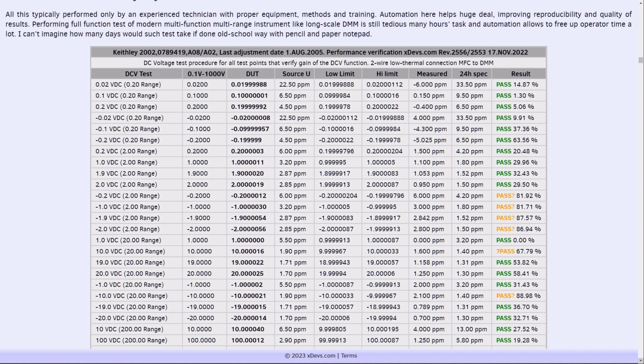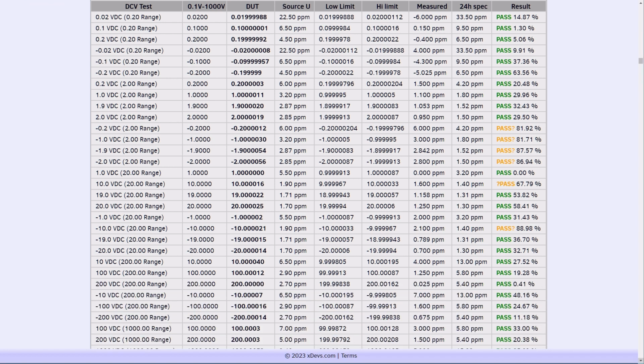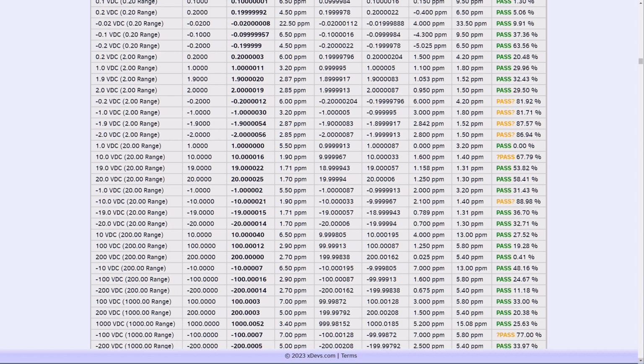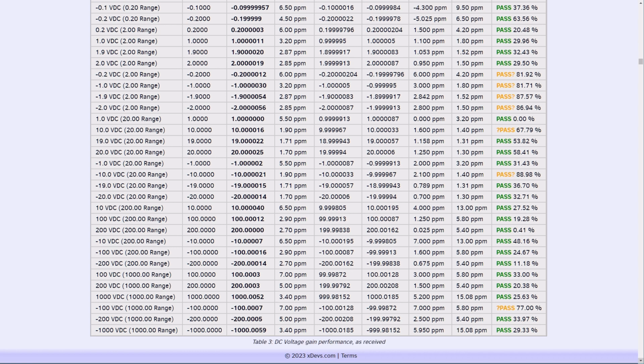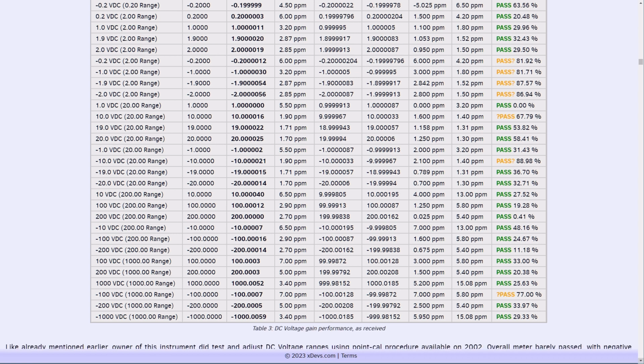Randall did adjust this meter's DC voltage function using the point cal function, so this explains why it is looking not too bad for a calibration that is overdue by 18 years. The negative 100 volt and 1 kilovolt ranges are also a little bit too tight to the edge, but again, we are testing against 24-hour specs, not 1-year specs.